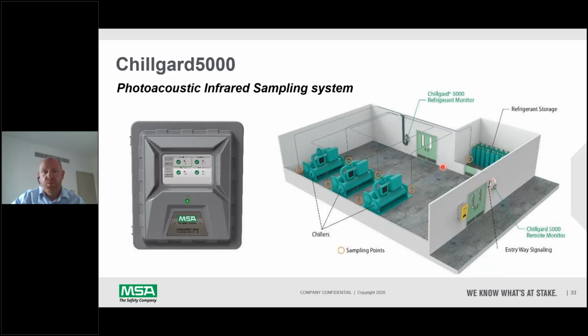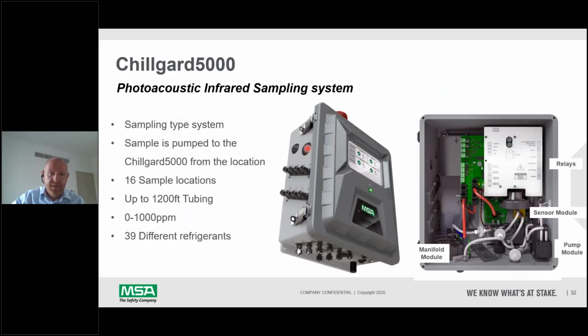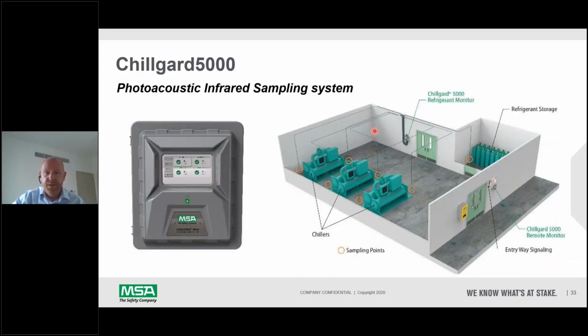A typical plant room would look like this image here. We have the sampling system, the Chillgard 5000, on the wall, and we have all the tubing which goes into these nozzles on the side or the bottom of the casing. There can be up to 16 different locations in the plant room. They generally go underneath the floor, or they can go on top of the floor and the roof, but they're installed at the base of the chiller. They have a filter at the end which filters out any dust or anything around the base of the chiller. It sequentially samples different points. Every 14 seconds, it will take suction from one sample, then move on to the next, and then the next. So you can get a much wider range of detection than by putting in one sensor per point. Only one sensor is needed for a large 16-point area.